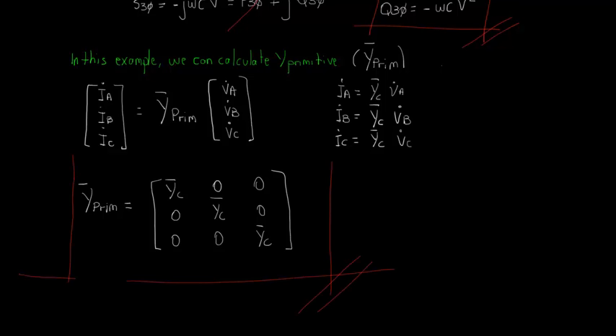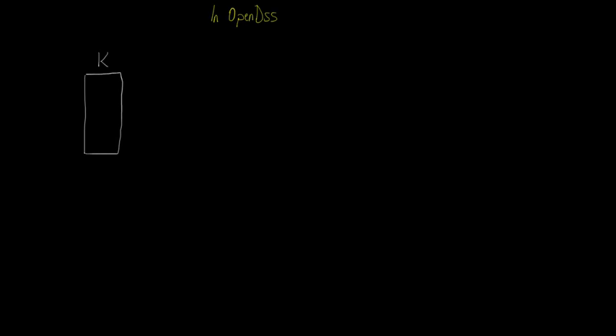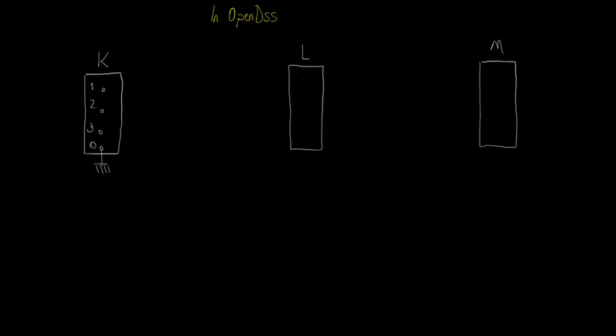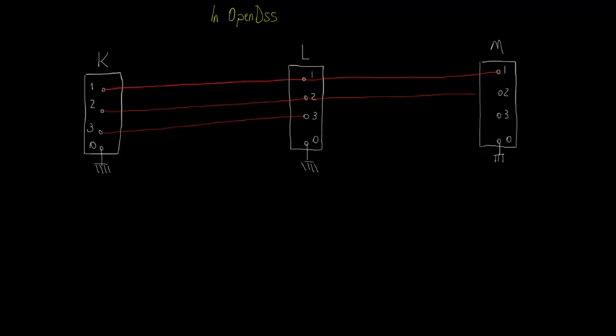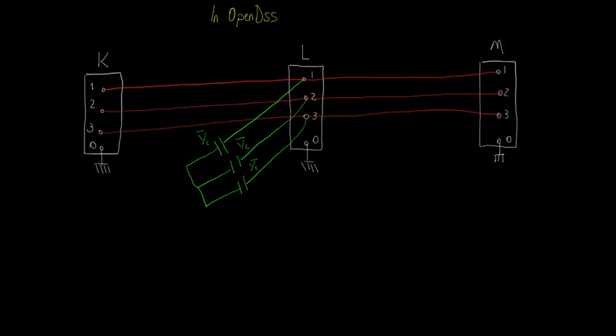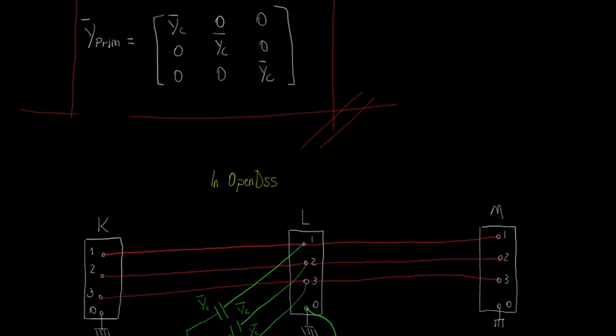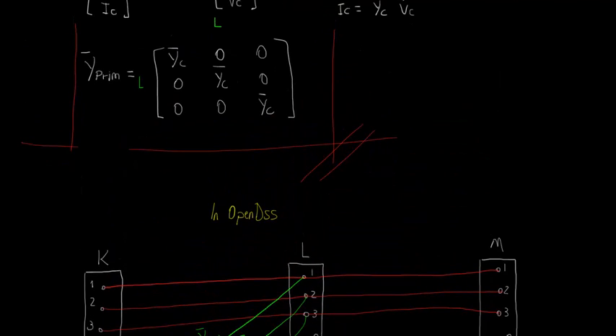Now, how can we define this element in OpenDSS? Let's assume that we want to connect our capacitor bank in a medium-voltage distribution line. In OpenDSS, we can model it as two three-phase lines connected between three buses, K, L, and M. The branches of the capacitor bank will then be connected to nodes 1, 2, and 3 of bus L, and its center node connected to node 0, which is always grounded. The Y-primitive matrix node's order is then 1, 2, and 3.